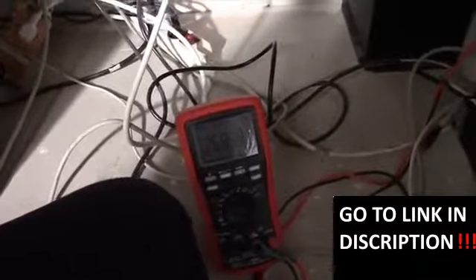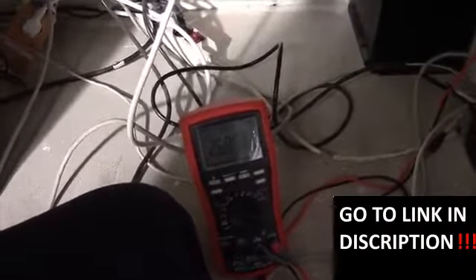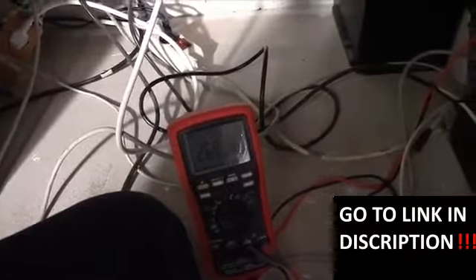So no unnecessary losses. The last cable essentially went round once or twice like that before going to the batteries, and combined with a bad connection at the clamps, that probably didn't help too much. I also raised the float charge voltage on the UPS because I realized that in my ignorance I had set it way too low.